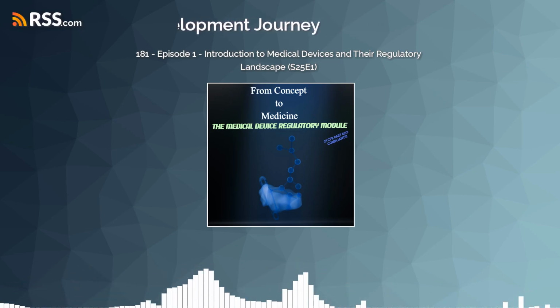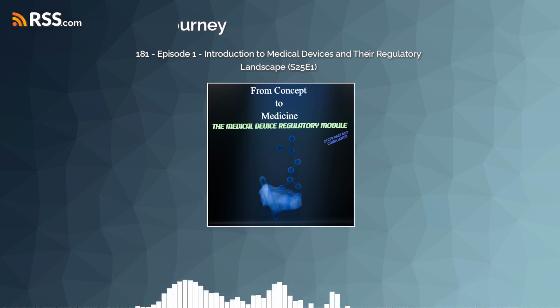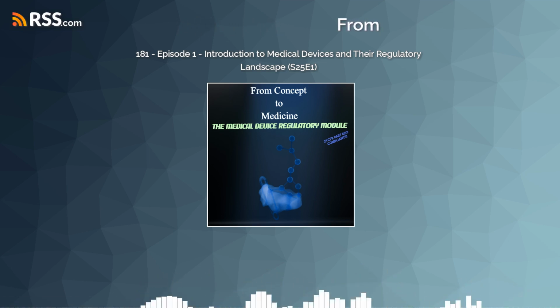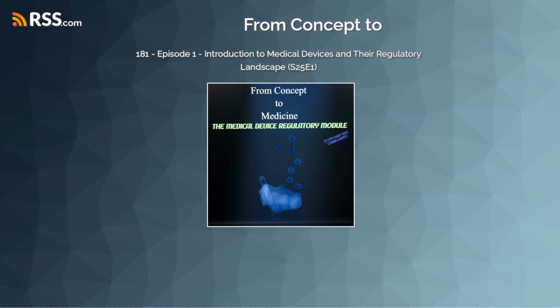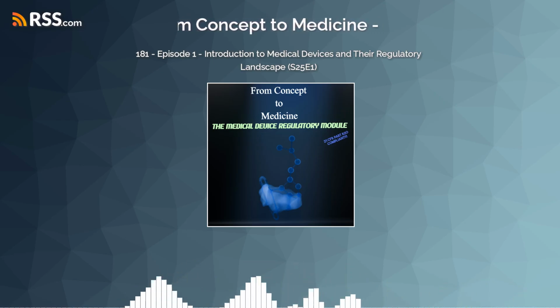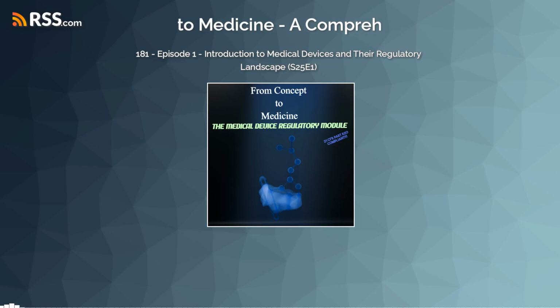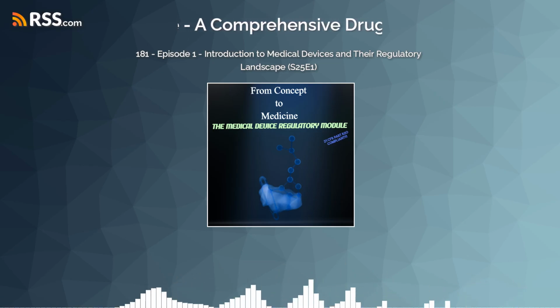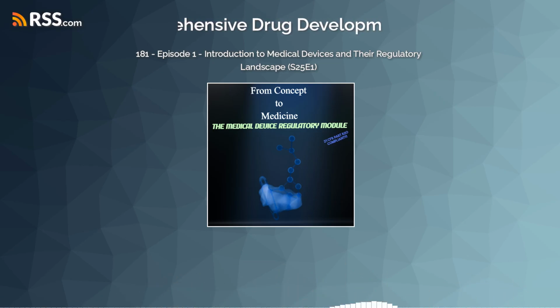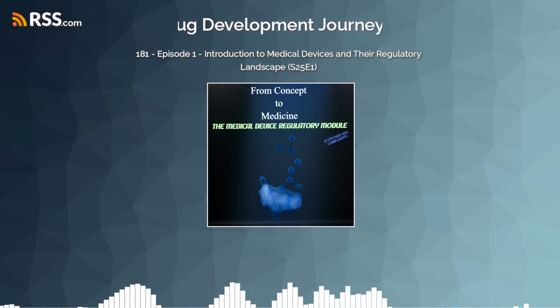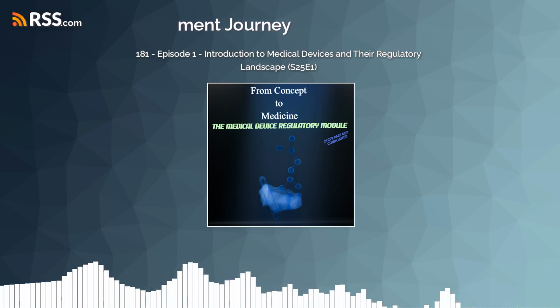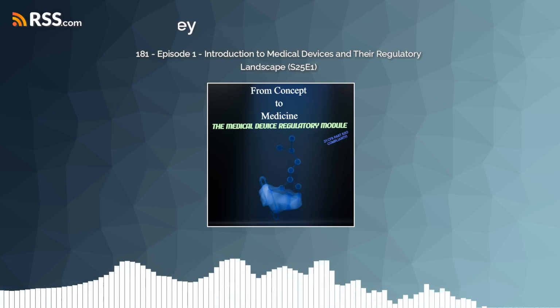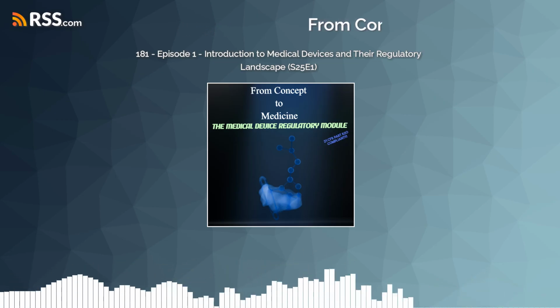Yes. ISO 13485 provides an internationally recognized framework for a medical device QMS. Many regulators around the world, including the FDA to a large extent, recognize or have harmonized their requirements with ISO 13485. It's really the global benchmark for device quality systems. Okay, ISO 13485. So what are the most critical elements of this QMS, this quality system?